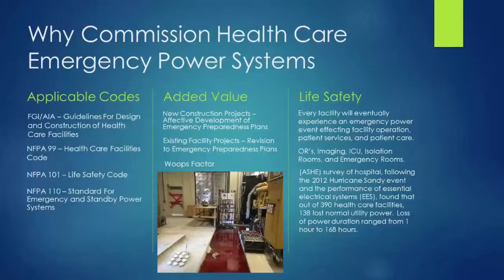So we get into, okay, how are we going to go about commissioning this? One thing to keep in mind is that the commissioning of the emergency power supply system is not a sprint. You're not going to bring this to your client and say, hey, next week we want to test this. Most of the ones I've worked on have taken months, 4 to 6 months, to coordinate to get to the point where we can safely do the emergency power system test, either on a brand new facility or an existing facility. So keep in mind, it's a duration, something you have to put long haul effort into to have success in.